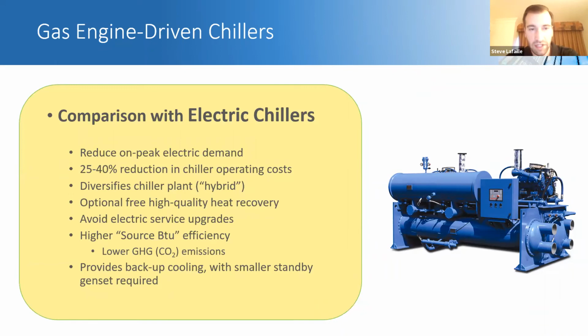But again, these are the major benefits: you're reducing your utility costs, your energy costs, and you give the owner diversification of their energy needs. This concept of hybrid chiller plants—we do that a lot, where we have some electric chillers and some gas chillers in a plant. It really lets owners play the rate structure: maybe run the gas chiller during the day during peak demand, run the electric units at night, or run the gas chiller to sync up with heat recovery needs and let the electric chillers do the rest, if you really want to optimize GHG emissions.